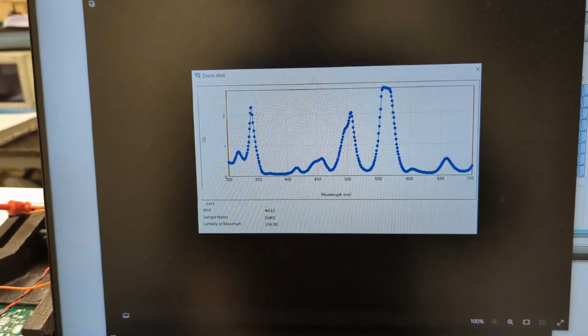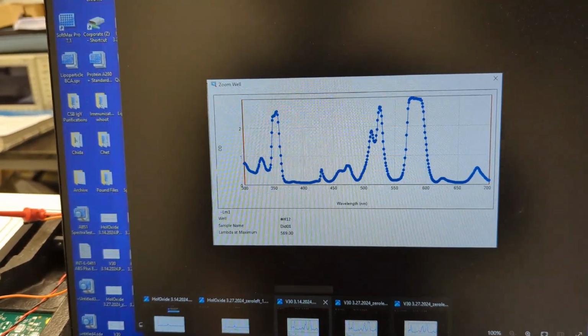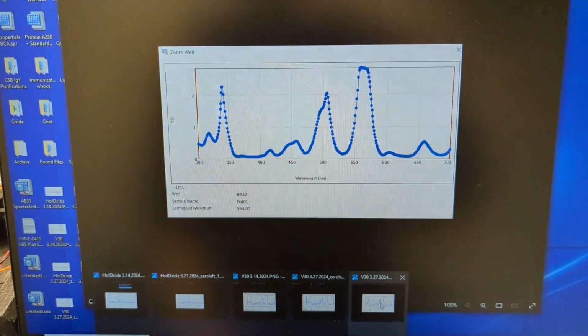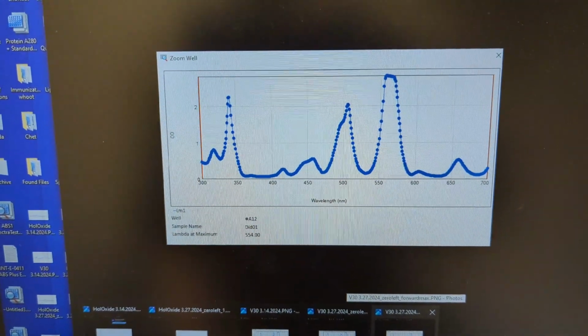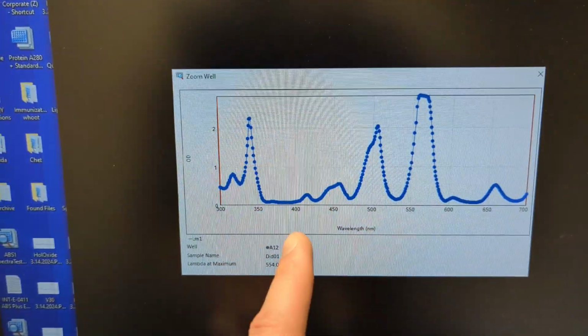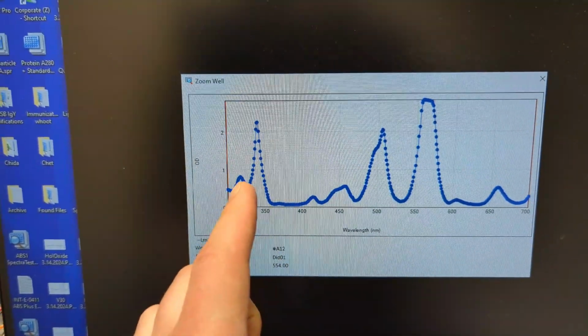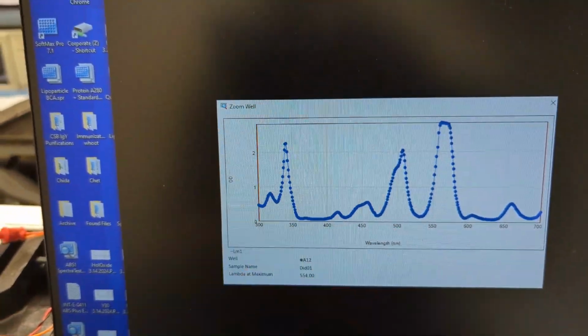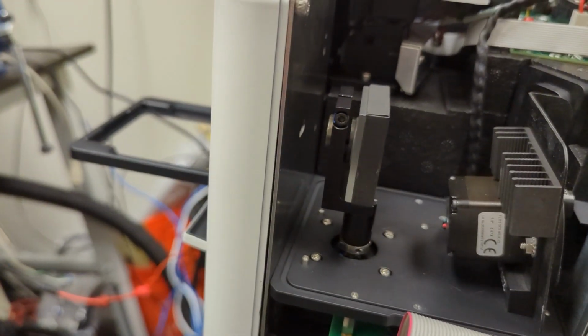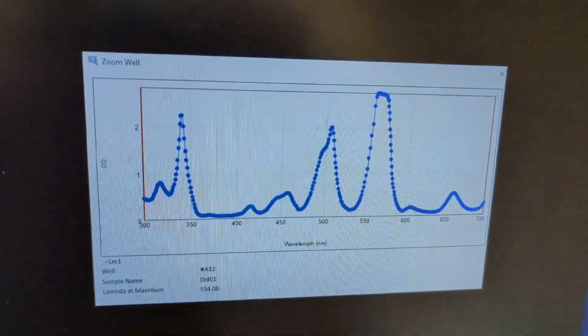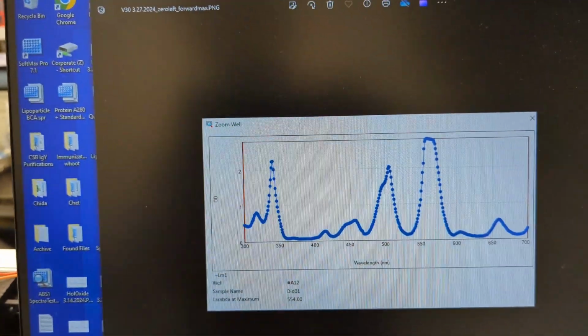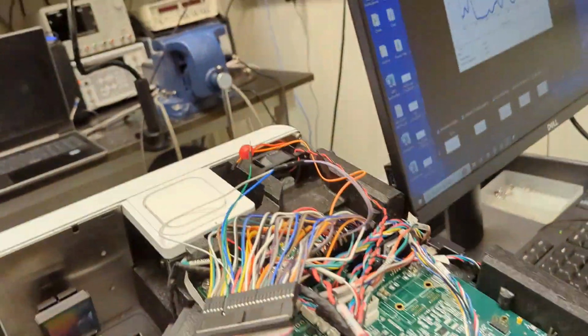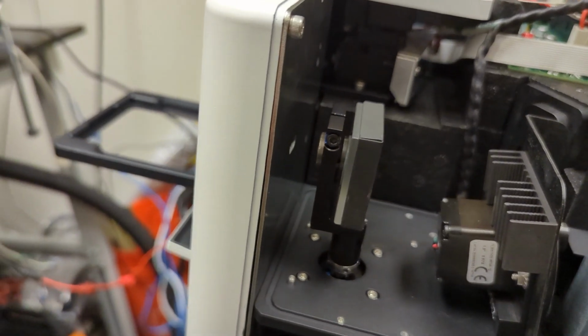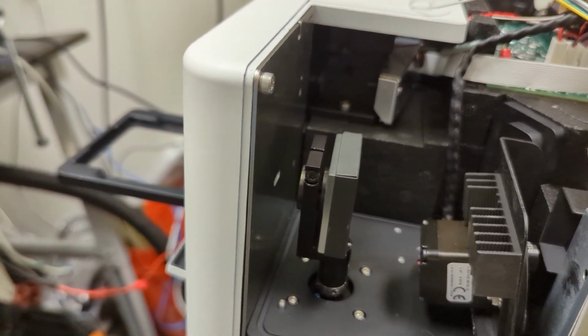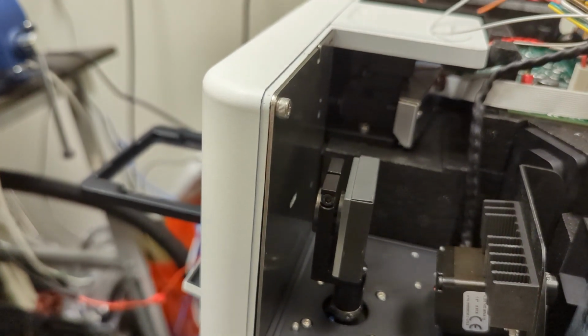This is with it all the way moved forward. And you can see the difference. So let me see if I can just switch between them. Look, that's passing, and that's failing, and you can see the difference in the resolution. You can see how all of the peaks were moved forward. So that's peak number 1, where it should be right around here. That's with this guy moved all the way to the front. All right, so if you're seeing something like this, or the wavelengths are too low in value, you need to move it back a little bit. And the same goes if the values are too high, higher than the standard, then you just move it a little bit forward.